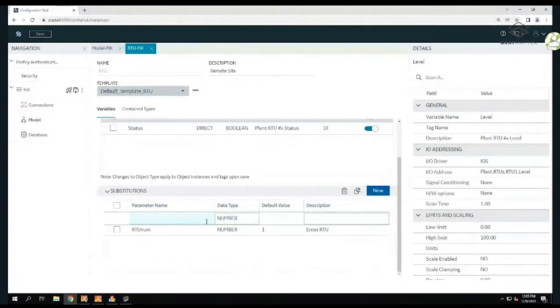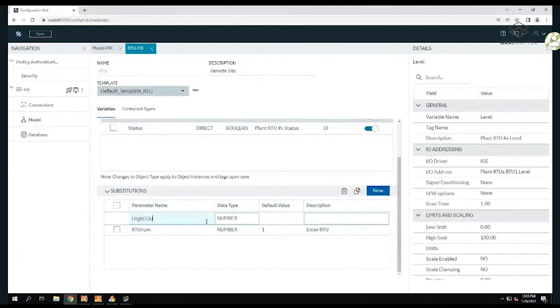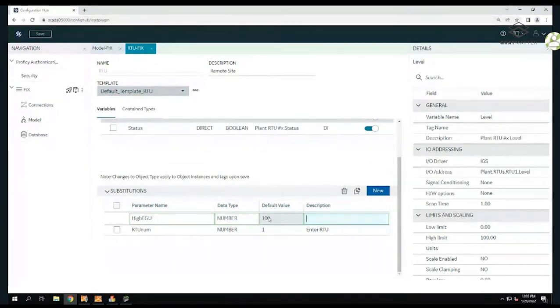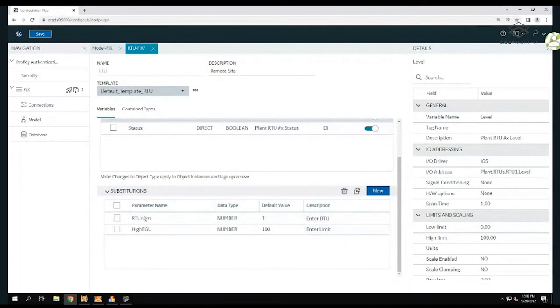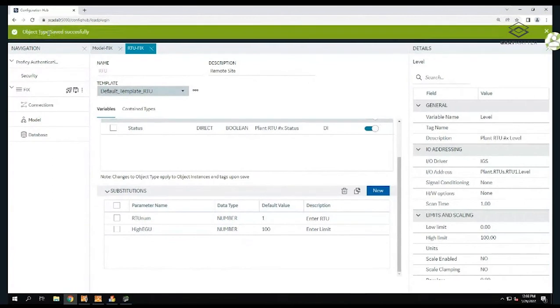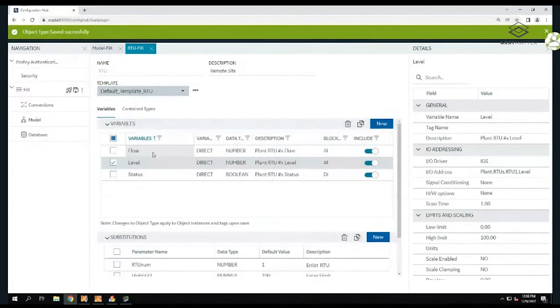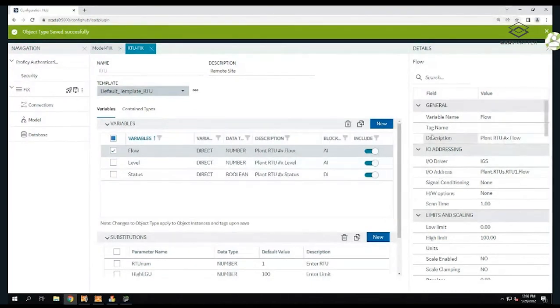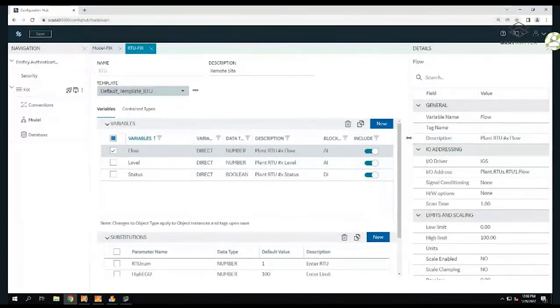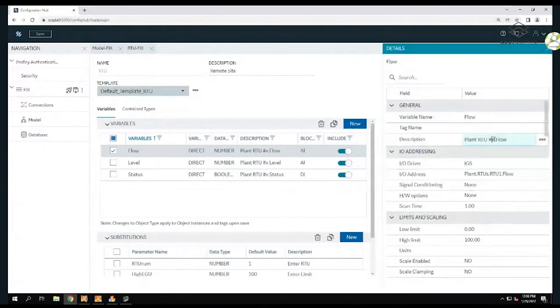I'm going to add one more placeholder here - my high engineering units. I'm going to change my high engineering units dynamically, scaled 0 to 100. These are substitutions I'm going to use in my system. I'll save with the top save button, then use these substitutions through my tag. I'll spend a little time modifying this template, and later you'll see we get a lot of value out of that. The X placeholder is what I'll be replacing dynamically with the RTU number.